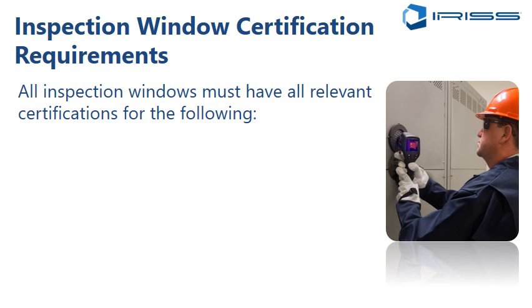So all inspection windows must have all relevant certifications for the following. UL 50V is the standard for infrared viewports. Now, many years ago we used to use UL 508, which was the standard for the electrical cabinets, but 4 or 5 years ago UL 50V was the standard that came out because infrared viewports were becoming more and more popular, and they were being used extensively.